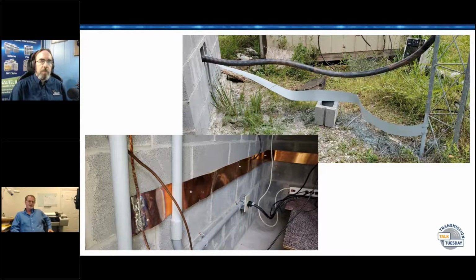So I had him order 4-inch copper strap, and we started pulling strap through there. When we ran it outside and strapped it to the tower leg, I made sure we brushed the galvanizing, got it all clean, and bolted it on. Cold galvanizing spray seems expensive until you have to replace a bunch of copper that some thief decided they had to have because it was shiny. I found out that cold galvanizing spray not only protects things, but most copper thieves look at it and think it's just some old sheet metal - it doesn't really get their attention.